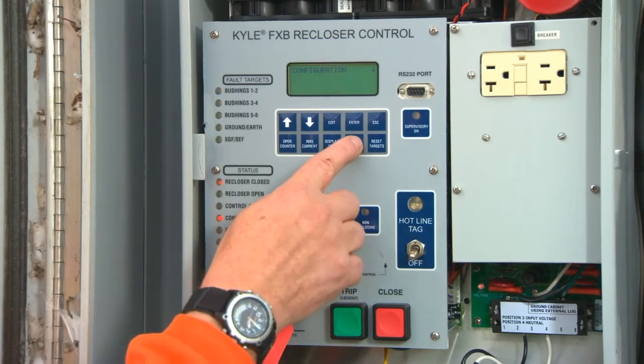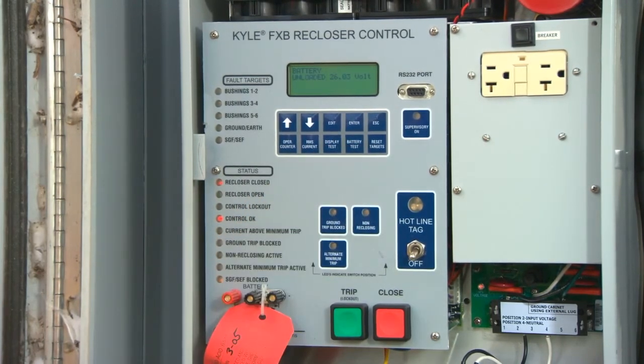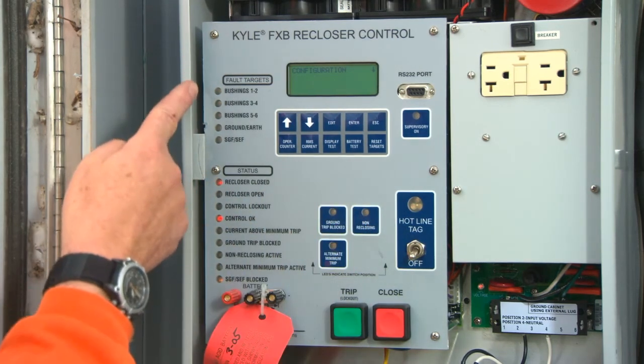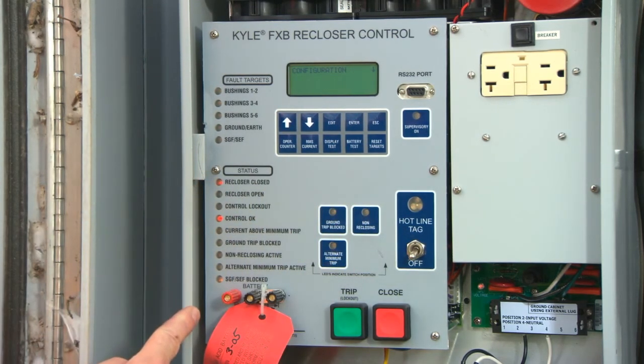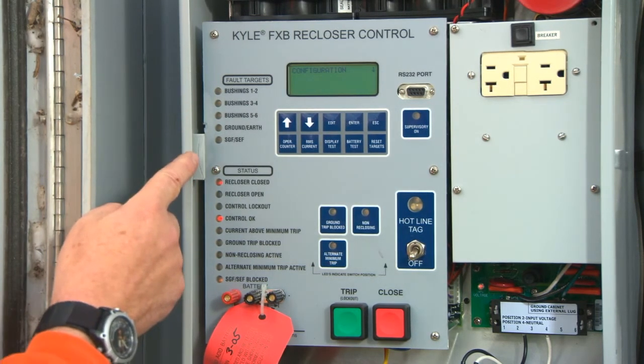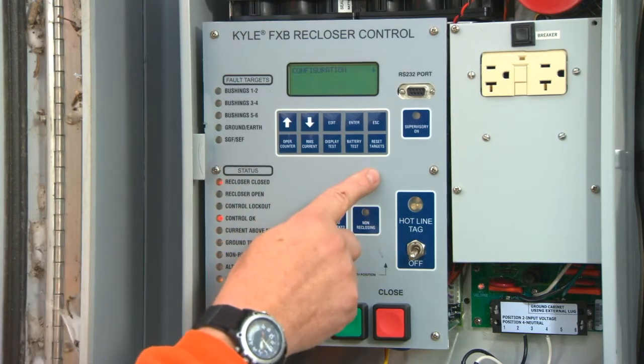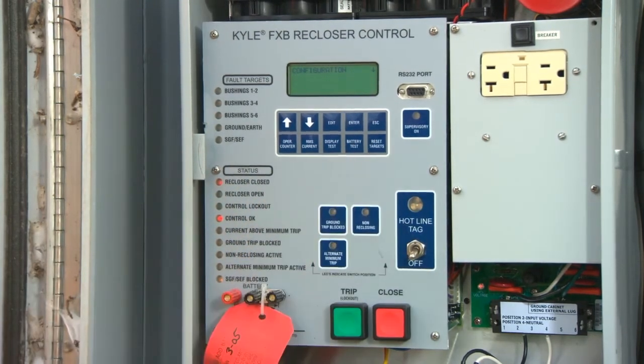Pressing the Battery Test button will perform a self-check on the battery. The screen now displays the unloaded state, which is the present voltage of the battery. It also displays the loaded state, which verifies that the battery is in working order. Reset targets. If you have any targets that have activated, when you close the control in, those targets will reset. If you wish to reset them manually, pressing the Reset Targets will return all of the indicators to their normal state.